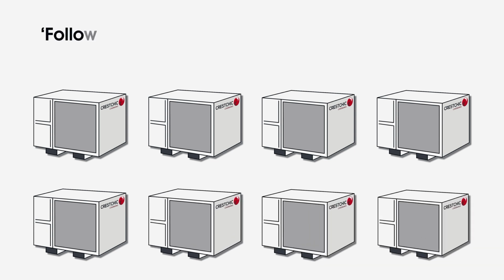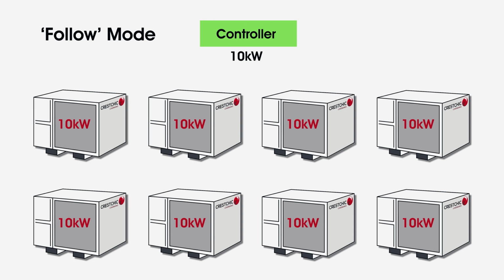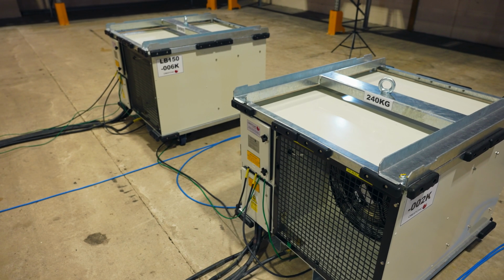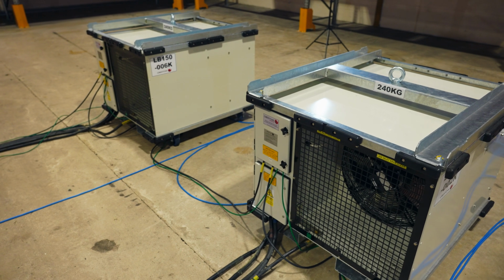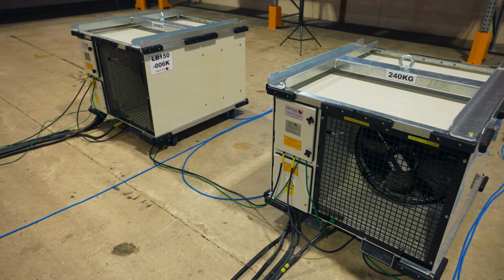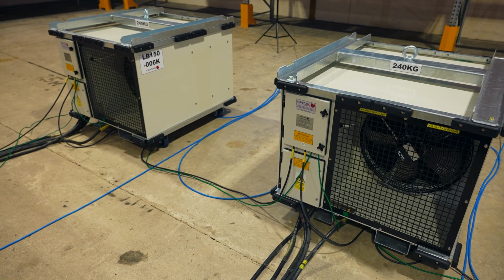The first one we call follow. With this mode, applying a load on the controller will apply this load to every load bank. For example, if there are 8 load banks connected together and 10 kilowatts is entered into the controller, 10 kilowatts will be entered into each load bank and therefore a total of 80 kilowatts will be present on the load source. This method is typically used when conducting air conditioning heat load temperature testing as part of a data center IST, where the heat can be increased from the load banks evenly and very accurately to where they are sited.